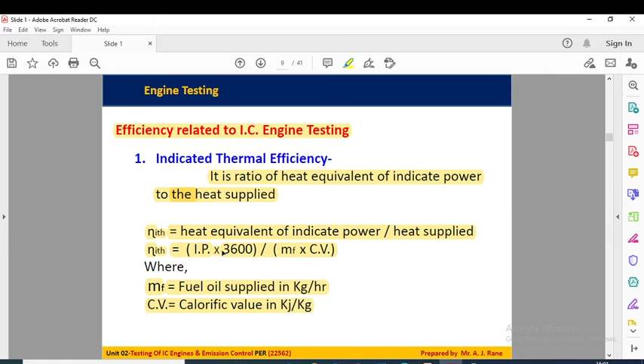Here it can be written as efficiency of indicated equals IP into 3600 upon MF into CV, where IP is the indicated power, MF is the fuel oil supplied in kg per hour, and CV is the calorific value of the fuel in kilojoule per kg. Here we are multiplying the indicated power by 3600 because normally we calculate power in watt, which is per second, and we need to convert this watt into kilojoule per kg per hour. That's why we need to multiply it by 3600.